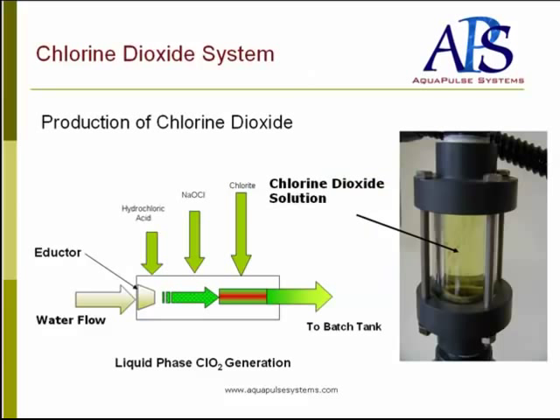The three-chemical system actually combines the three chemicals — sodium chlorite 25%, sodium hypochlorite 12.5%, and 15% hydrochloric acid — together in a water stream, causing a vacuum that pulls the chemicals in together. This is an infinitely safe system, since if the water shuts off, it will stop pulling the chemicals in and stop making chlorine dioxide. The chlorine dioxide is safely routed to a batch tank from where it's distributed to the process.